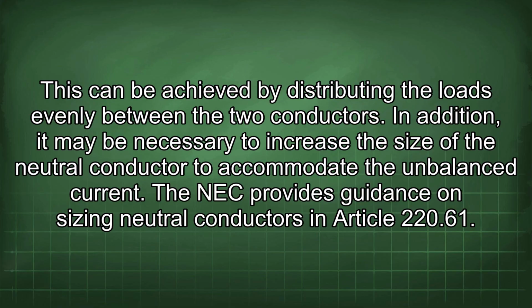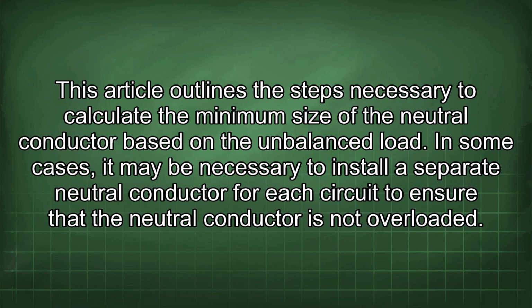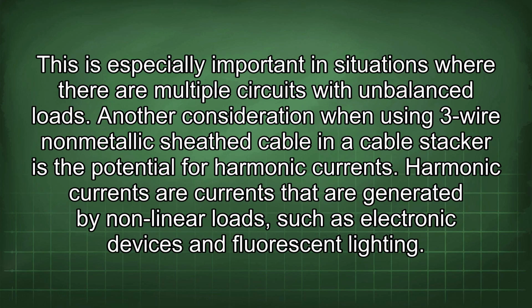In addition, it may be necessary to increase the size of the neutral conductor to accommodate the unbalanced current. The NEC provides guidance on sizing neutral conductors in Article 220.61. This article outlines the steps necessary to calculate the minimum size of the neutral conductor based on the unbalanced load. In some cases, it may be necessary to install a separate neutral conductor for each circuit to ensure that the neutral conductor is not overloaded. This is especially important in situations where there are multiple circuits with unbalanced loads.